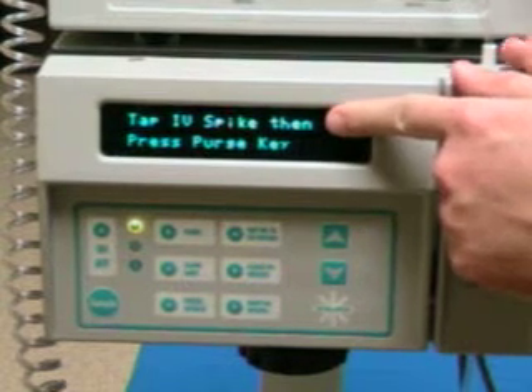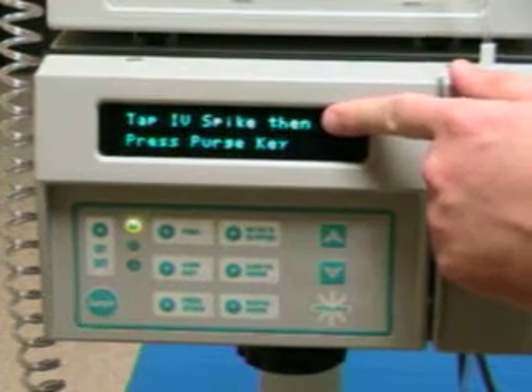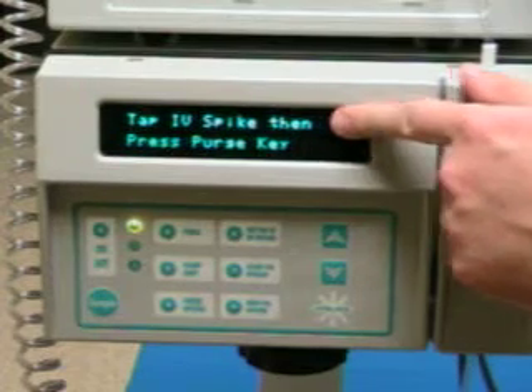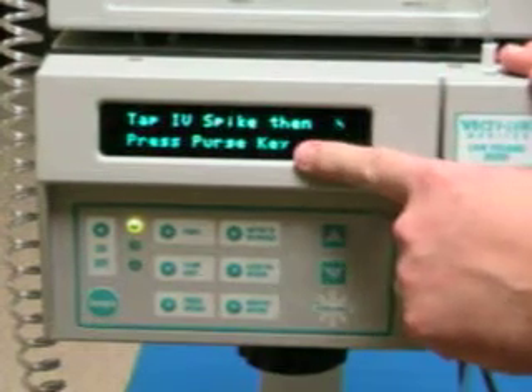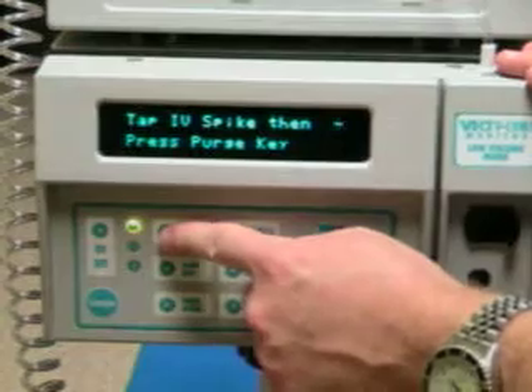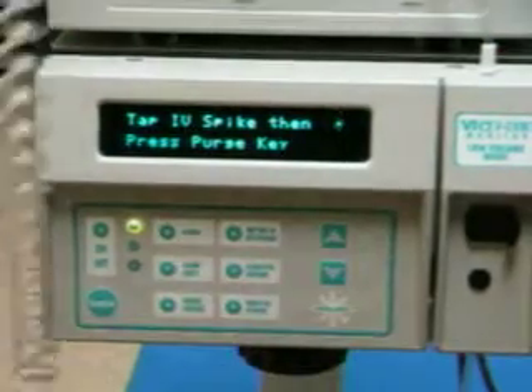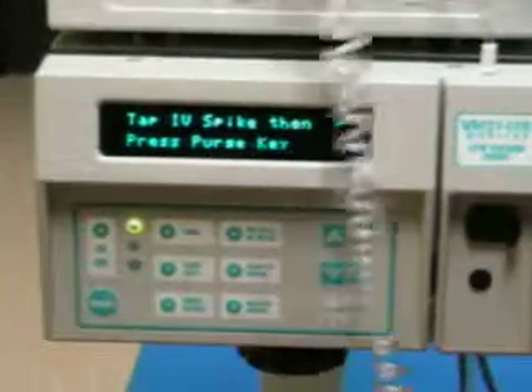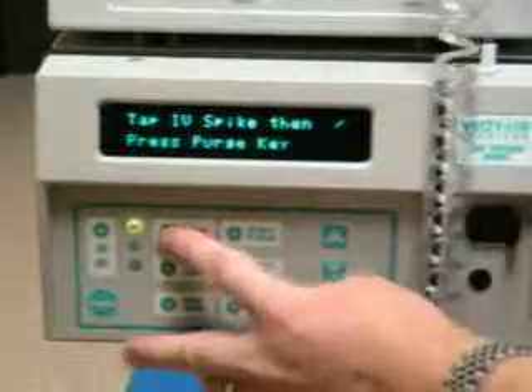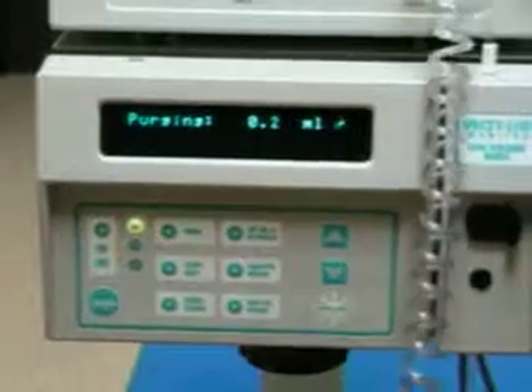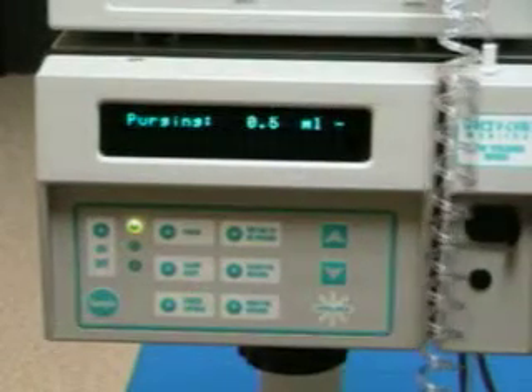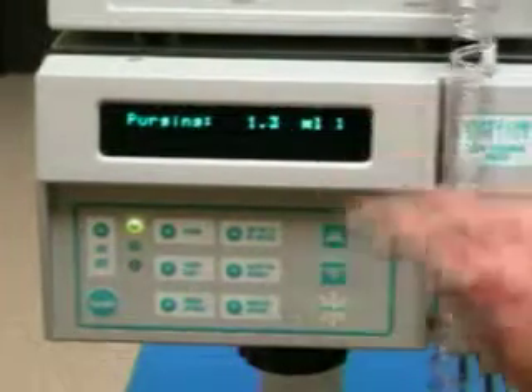This is referring to the IV spike that we spiked the bag with, so we'll give that a few taps just to clear the air. Then we'll press the purge key. Now this purge key is important because remember we didn't prime this curlicue tubing. This is the portion where it's going to prime all that tubing, and then when it does this 15 mil purge, which I'll start, hit the purge key, and again it's going to start a 15 mil purge.